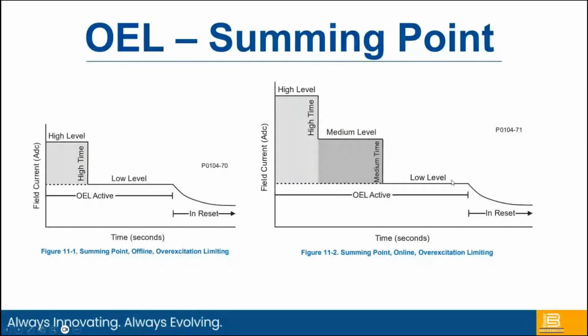Maybe you can continue to operate on the overexcitation limiter indefinitely, as long as you don't see a problem. As long as load is not changing and you don't run into a protective element that trips you off, then you're fine if the OEL is set up correctly. But if you're hitting the OEL under normal operating conditions, then you probably have a problem somewhere. It might be a problem within the brushless exciter or your slip rings, but typically you don't operate on your OEL very long. You might bump into them occasionally, but it should quickly come off that limiter as you're going through different load transitions.